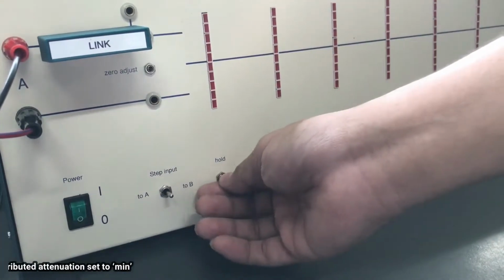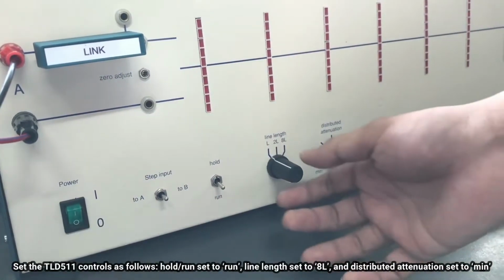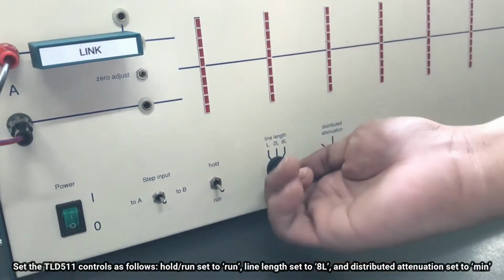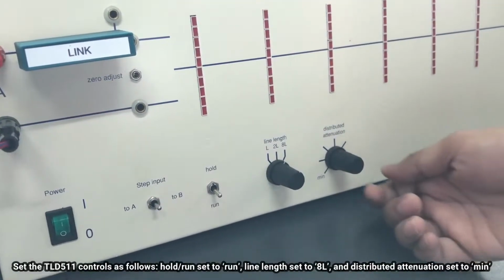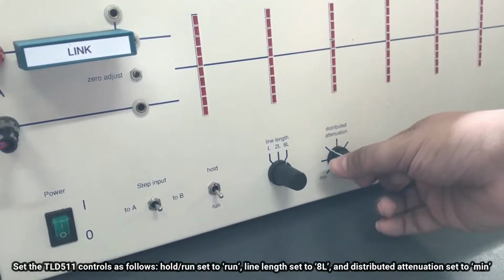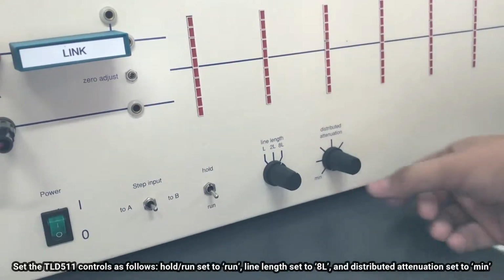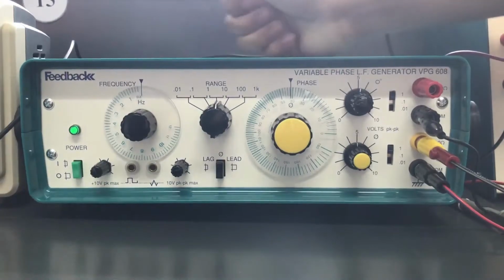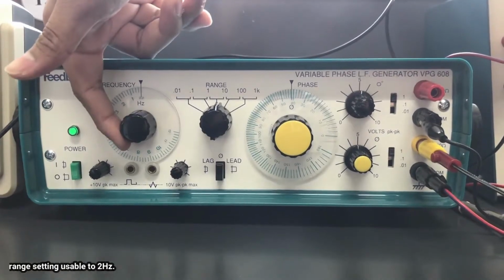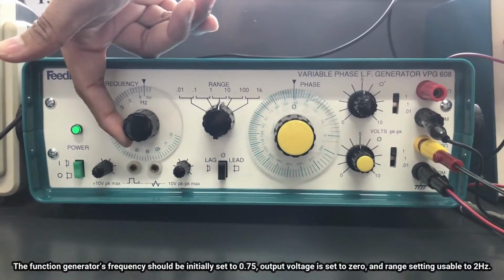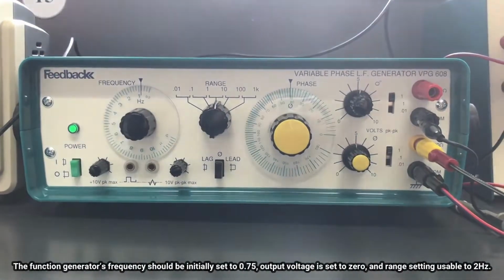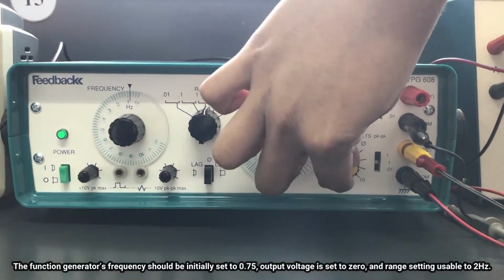Set the TLD511 controls as follows. Hold run, set to run, line length set to 8L, and distributed attenuation set to minimum. The function generator's frequency should be initially set to 0.75 and the output voltage is set to 0.